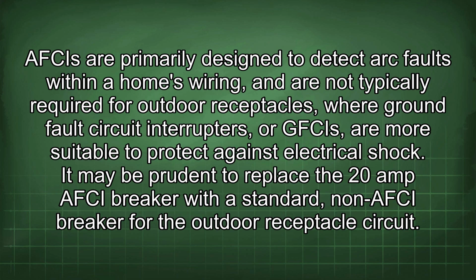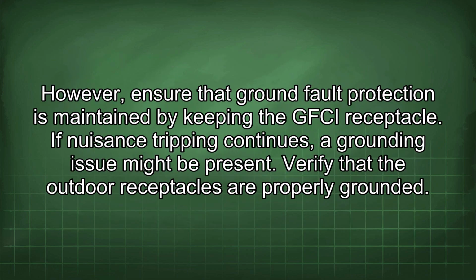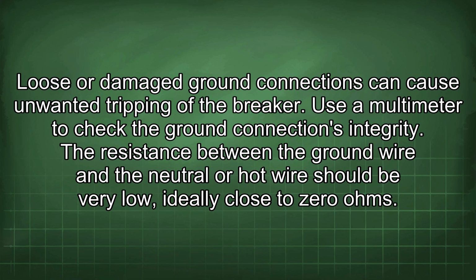It may be prudent to replace the 20-amp AFCI breaker with a standard non-AFCI breaker for the outdoor receptacle circuit. However, ensure that ground fault protection is maintained by keeping the GFCI receptacle. If nuisance tripping continues, a grounding issue might be present. Verify that the outdoor receptacles are properly grounded. Loose or damaged ground connections can cause unwanted tripping of the breaker.